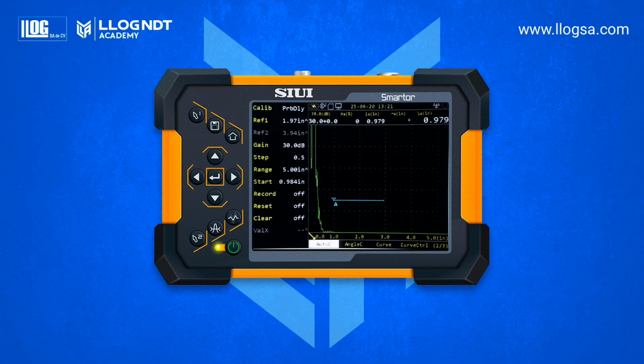Finally, in the Auto Calibration submenu, you will find 3 calibration options. First, probe delay. The instrument calculates the probe delay using a single known reference point. 2. Velocity. It calculates the material velocity based on the propagation time difference. And 3. Velocity plus probe delay. This is the most commonly used method and involves a 2-point calibration.